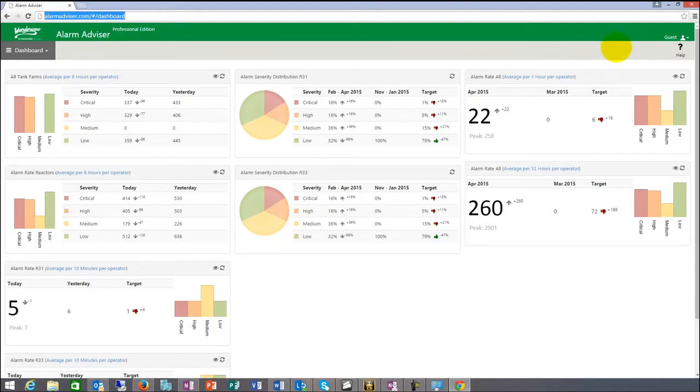The alarm logger feeds it data from the alarms from InTouch. It has to be in detailed mode. A database that is in consolidated mode does not work with this system. So if you have a logger, you have to set your logger up for detailed and not for consolidated, and that has to do with the type of record sets.